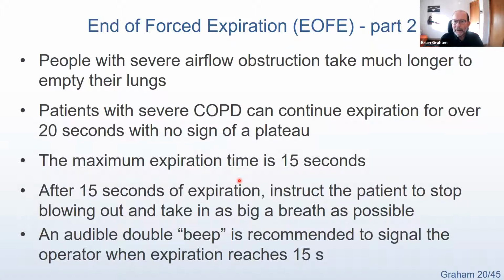So the second way that we can accept the end of forced expiration is for people with COPD or obstruction who just take a long time to empty their lungs. And people with COPD can expire for 20 seconds or more without any sign of a plateau. So what we've said is the maximum expiration time is 15 seconds. Now, this was kind of mentioned in the 2005 guidelines, but it wasn't explicit, and we're making it explicit here. So after 15 seconds, you instruct the patient to stop blowing out, take in as big a breath as possible. And of course, they can blow out for more than 15 seconds, but there's really not any important clinical information by extending the test, and you're only giving the patient a lot more grief.